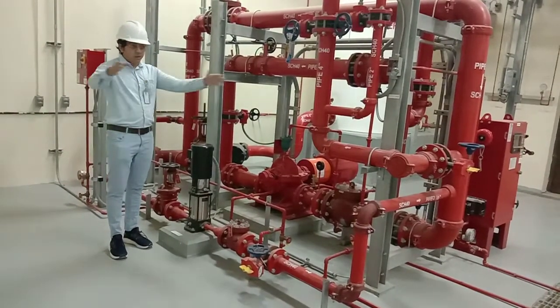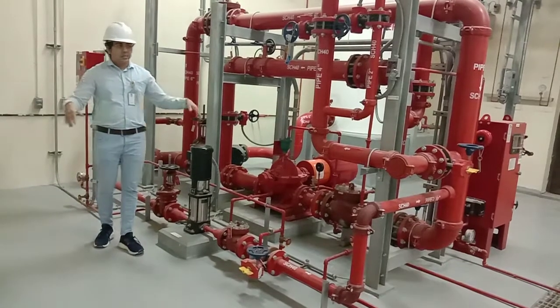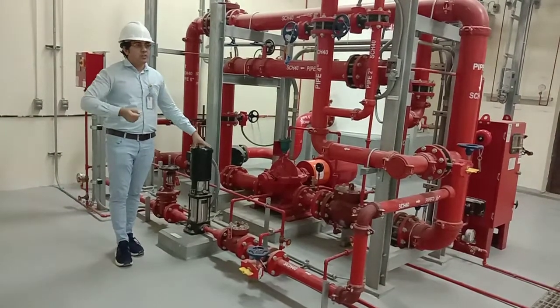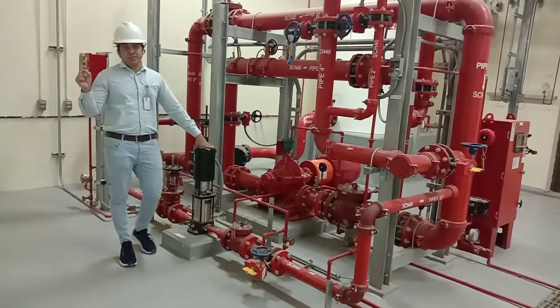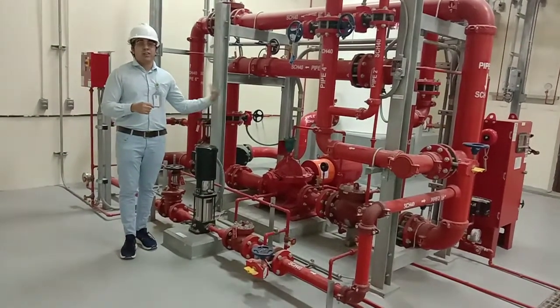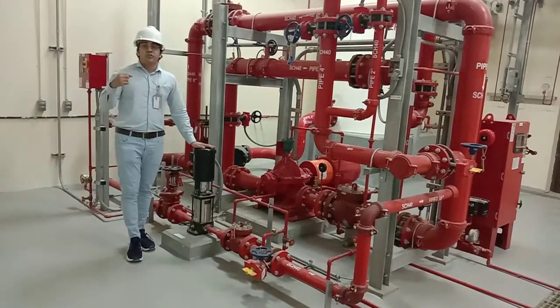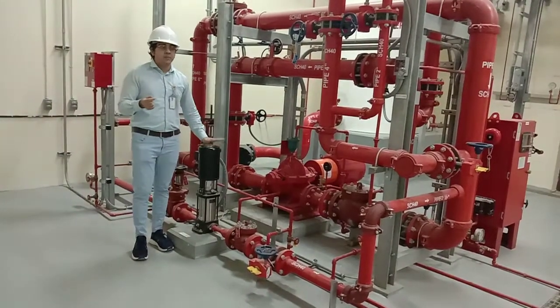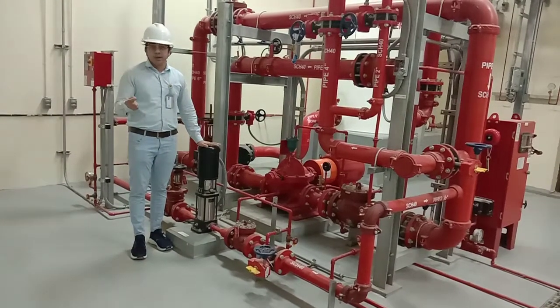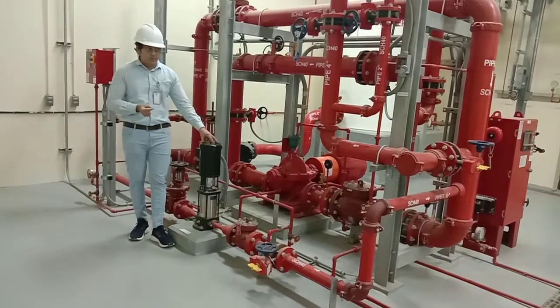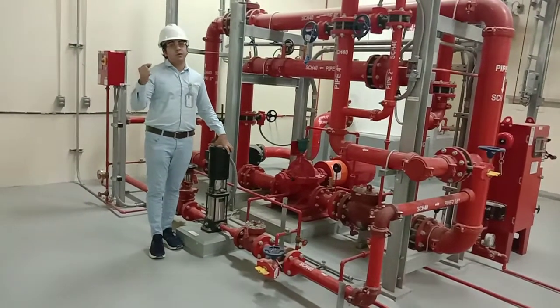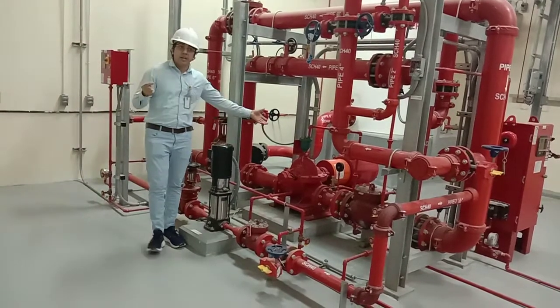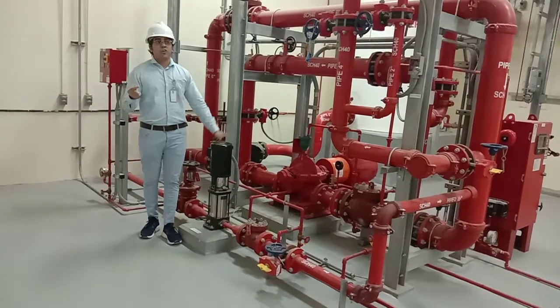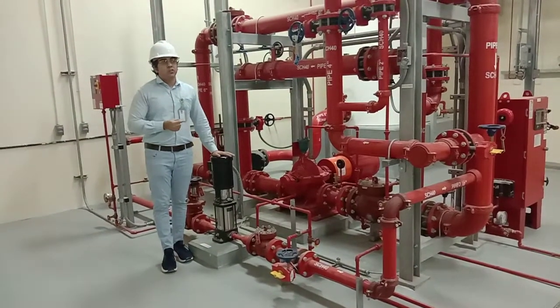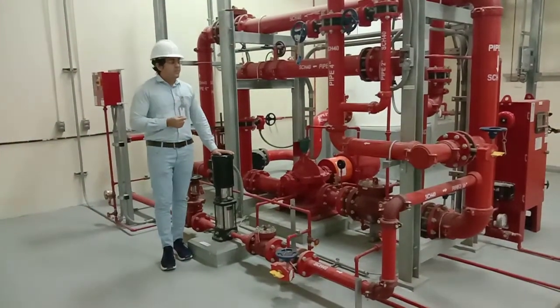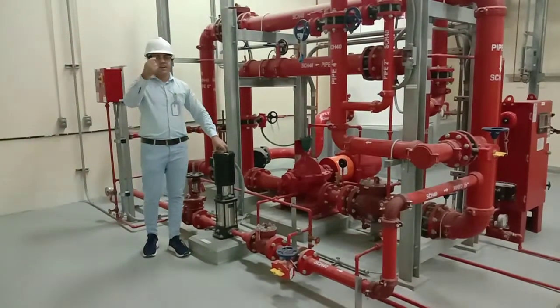Consider, let's say, that we have underground fire water networks, right? For underground fire water networks, we have to size the jockey pump based on 1% of the main fire pump capacity. If your fire pump is 1000 GPM, rated at 140 psi, the jockey pump needs to be 1% of 1000, which is 10 GPM. So the minimum size of the jockey pump should be 10 GPM. Coming back to the pressure, the jockey pump pressure should be at least 10 psi higher than the main pump. In that case, if our main pump is rated for 140 psi, the pressure for the jockey pump should be at least 150 psi. This is because the jockey pump is just to maintain the pressure.